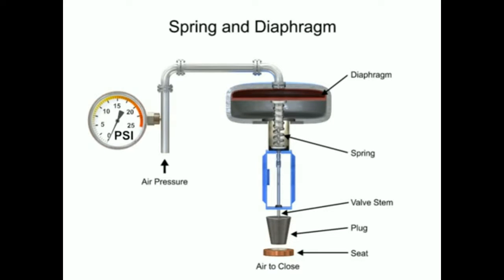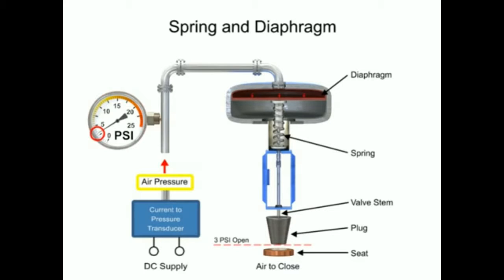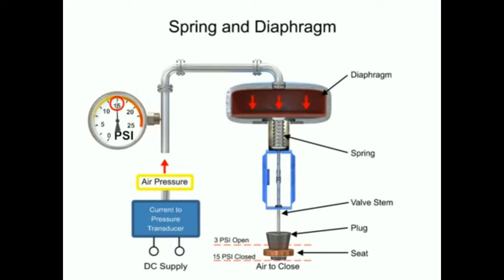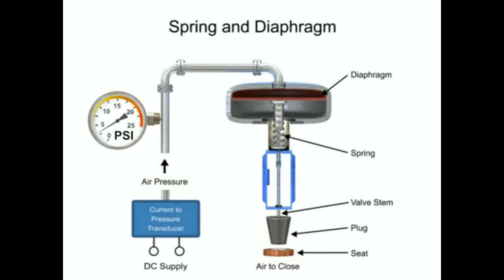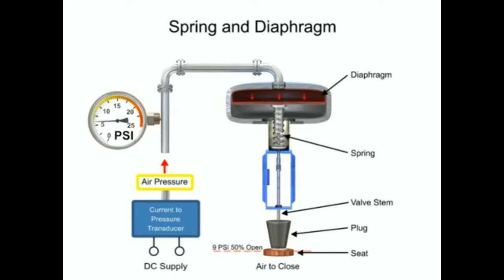To vary the position of the restrictor and flow through the valve, a current-to-pressure transducer can be used to provide a 3 to 15 PSI signal to the diaphragm. At 3 PSI, the valve is maintained open, and at 15 PSI, the valve is maintained closed. Pressures between the 3 to 15 PSI range proportionally change the flow of the valve. For example, a pressure of 9 PSI applied to the diaphragm moves the spring and valve stem to 50% of operating range.